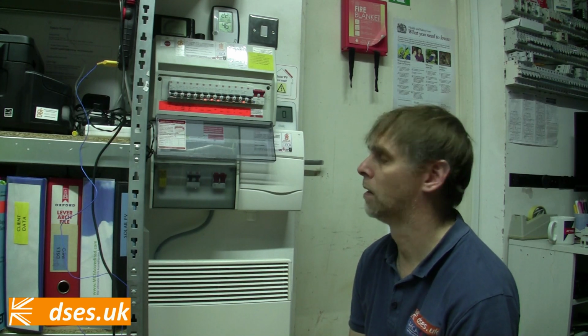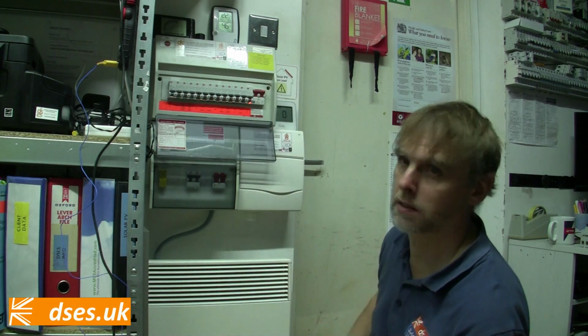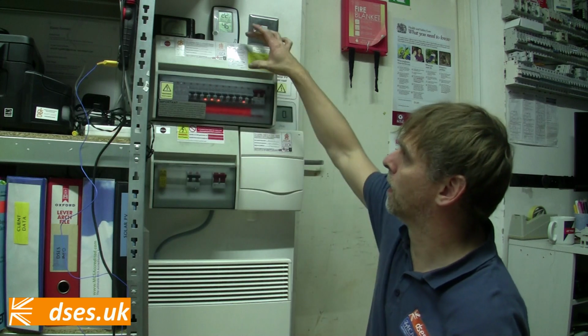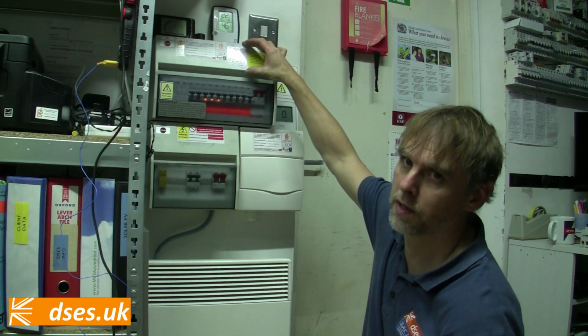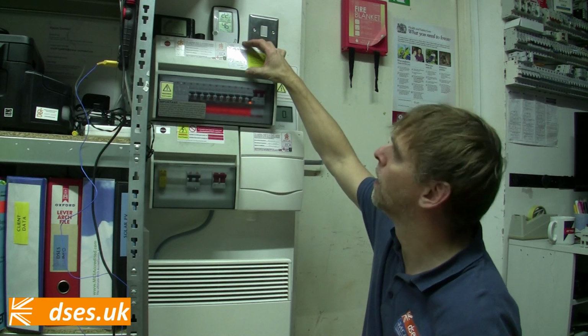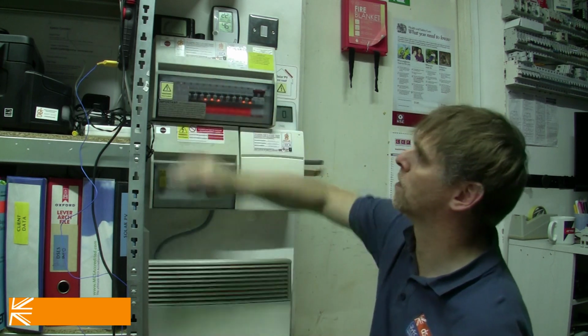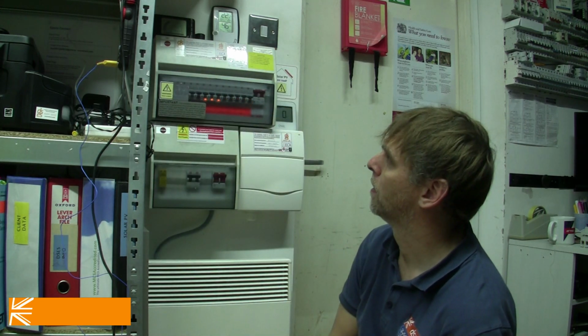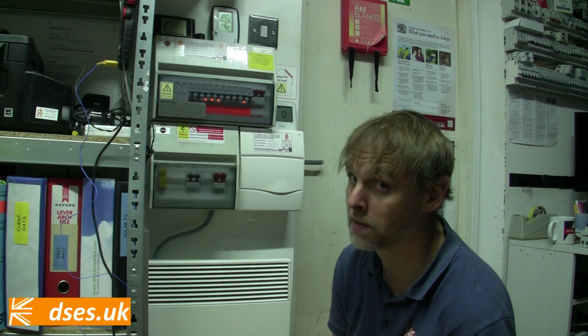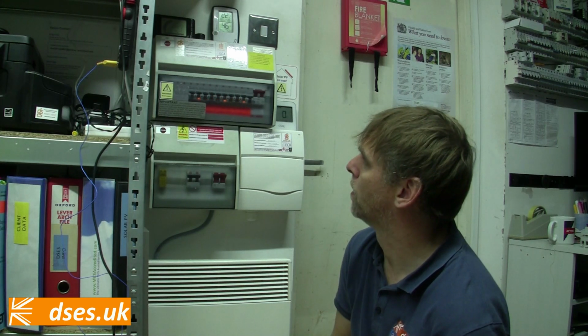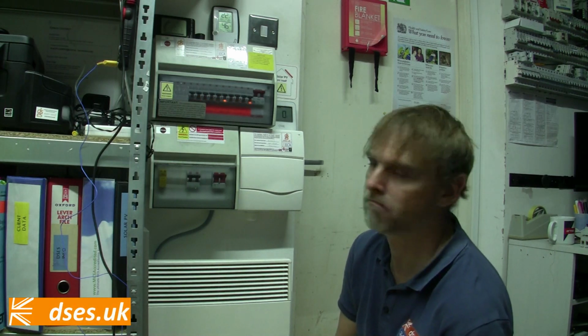So, well, I'm pretty bulletproof apart from the old plastic casing. But I've got the sticker up there to say what the fault indicators are, and I've got my new Test and Inspect sticker on there because I will be providing a new installation certificate, a new Part P certificate. Yes, why not? Maybe I should film that. And that's that signed off for up to another 10 years. I'll stick a 10-year ticket on that.